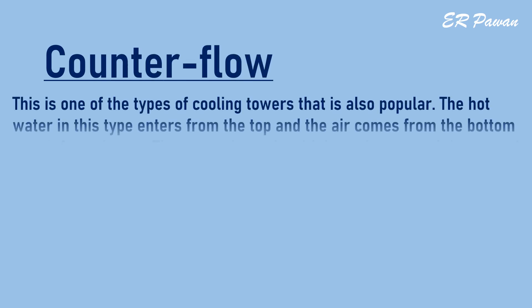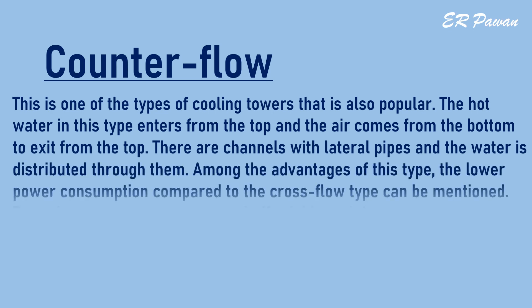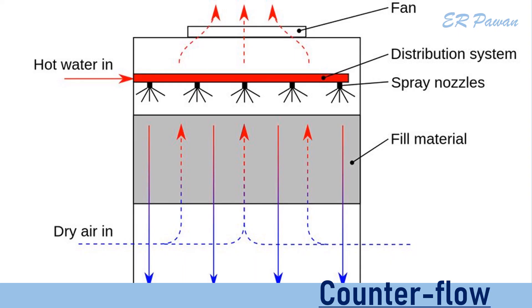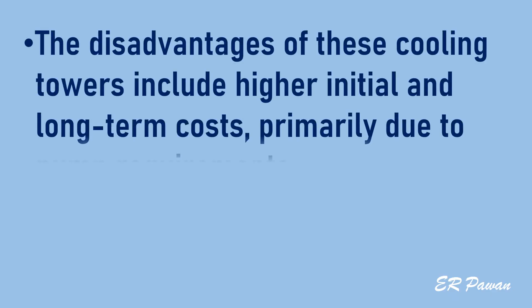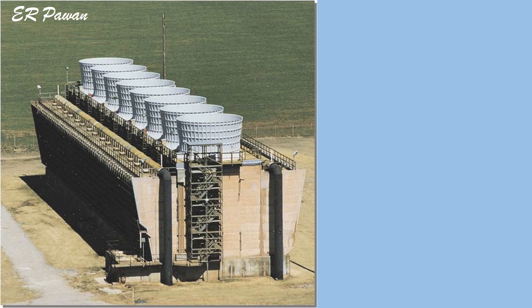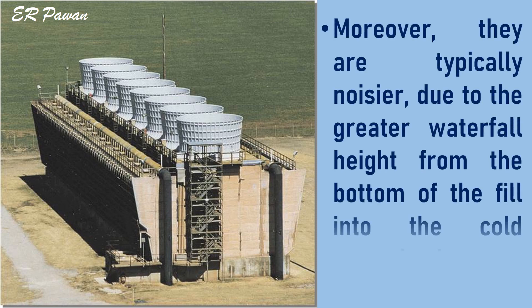Counter flow: this is one of the popular types of cooling towers. The hot water enters from the top and the air comes from the bottom to exit from the top. There are channels with lateral pipes and the water is distributed through them. Advantages include lower power consumption compared to cross flow, easy and affordable maintenance, and a more compact build. The breakup of water into spray makes heat transfer more efficient. Disadvantages include higher initial and long-term costs primarily due to pump requirements.